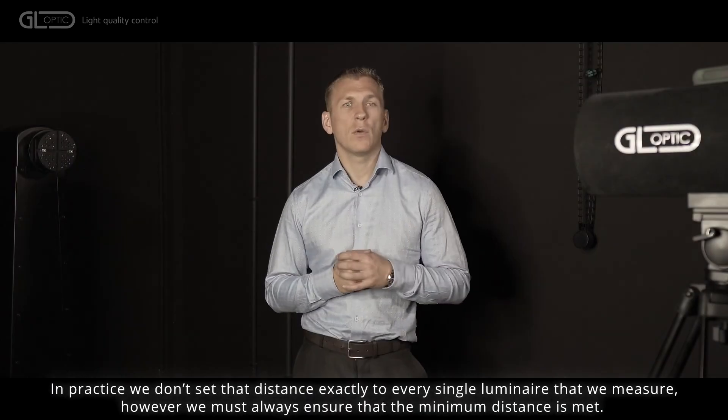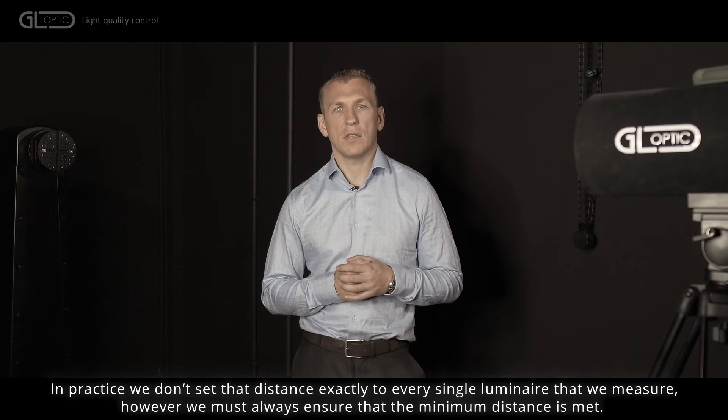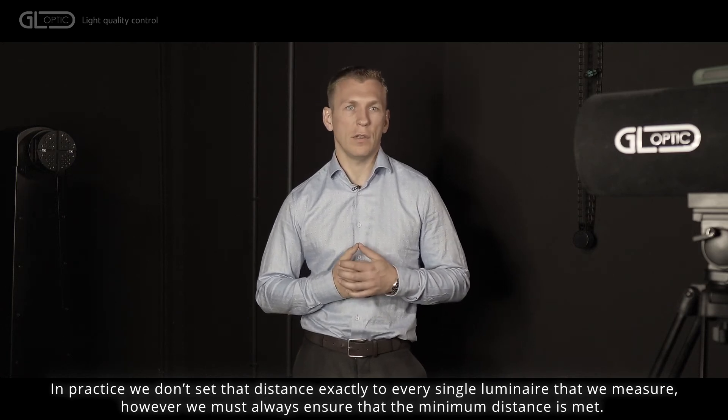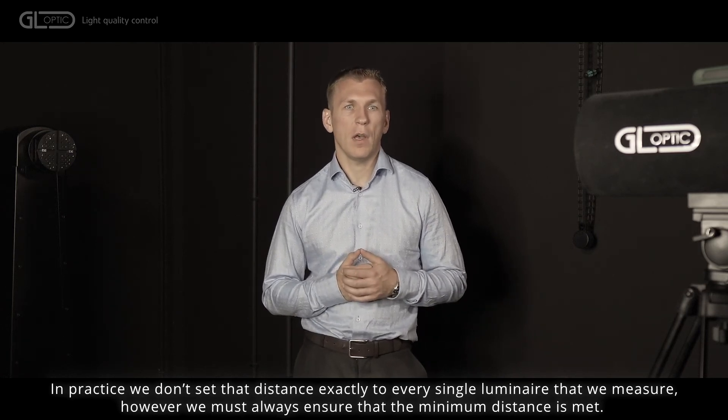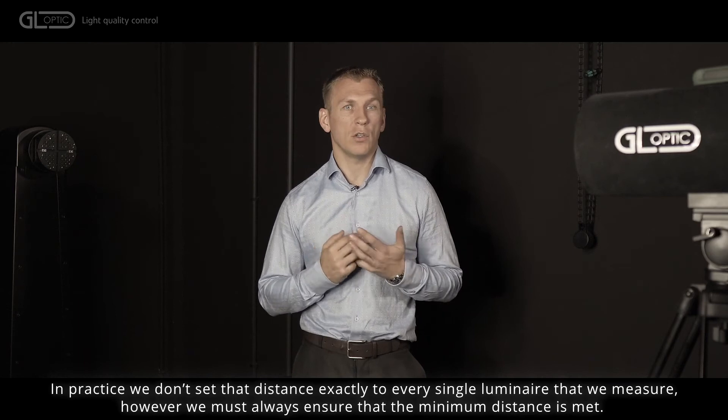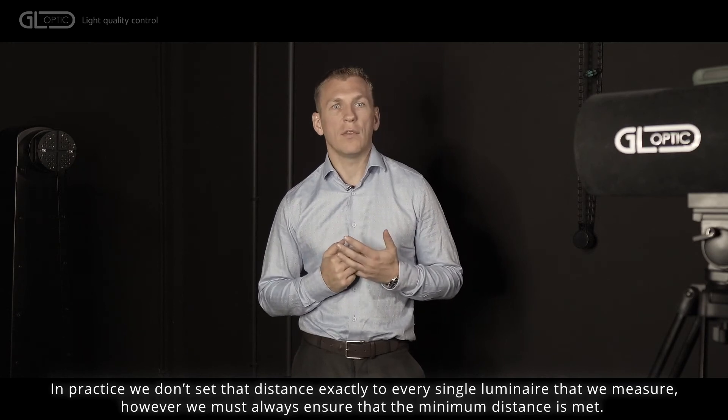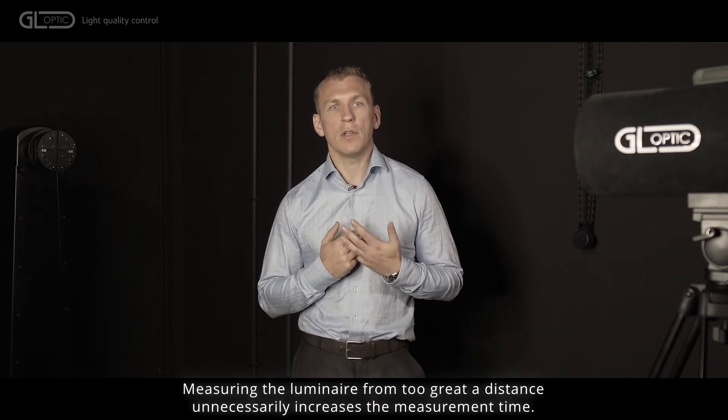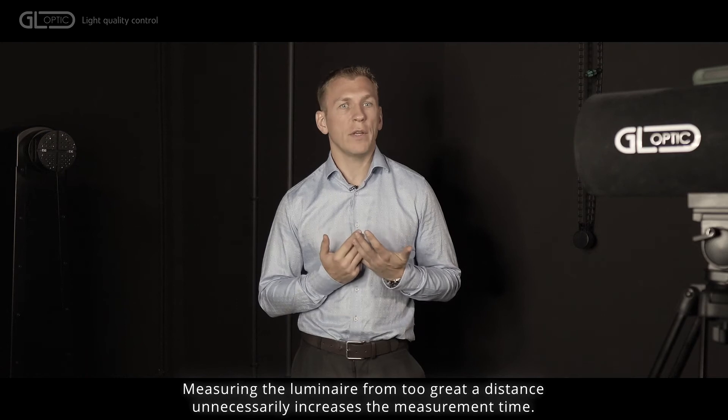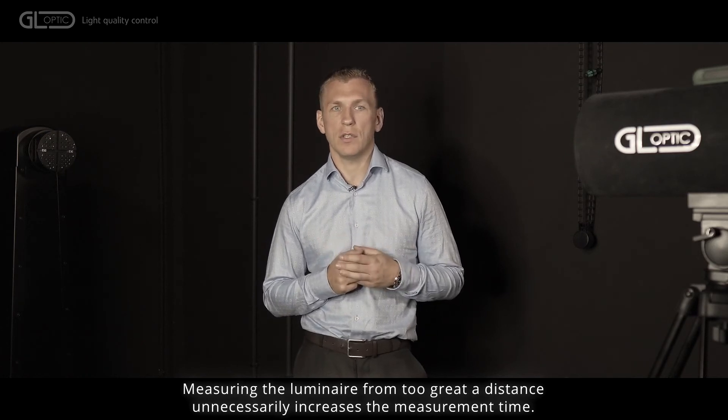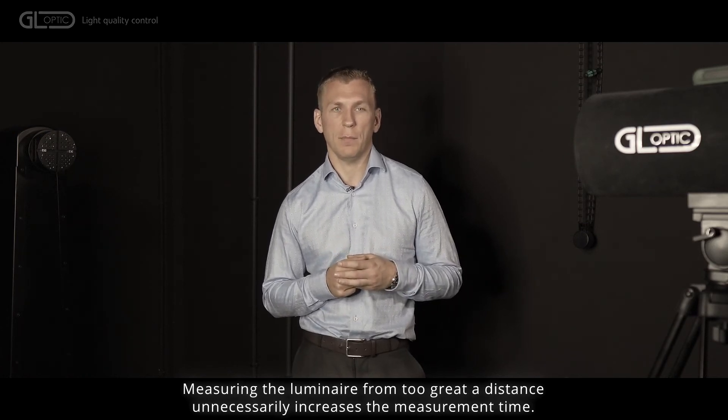In practice, we don't set that distance exactly to every single luminaire that we measure. However, we must always ensure that the minimum distance is met. Measuring the luminaire from too great distance unnecessarily increases the measurement time.